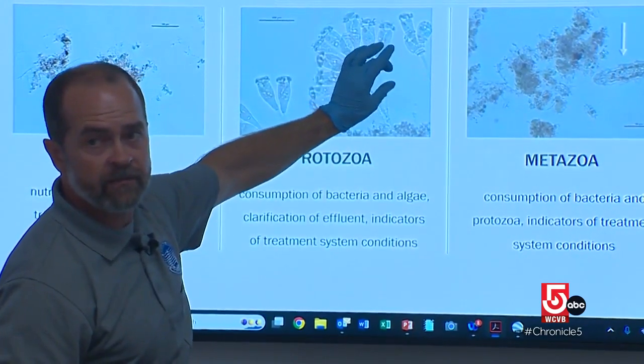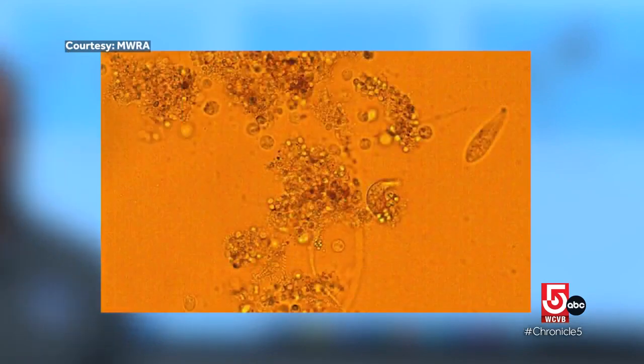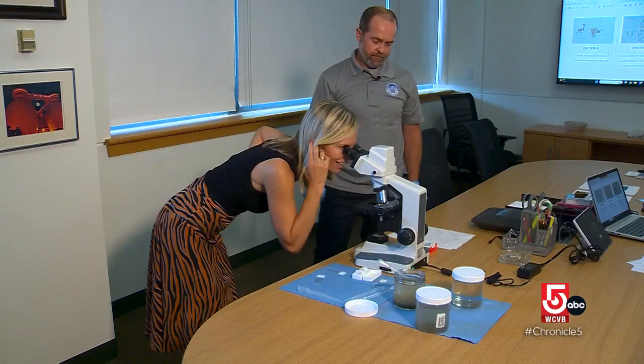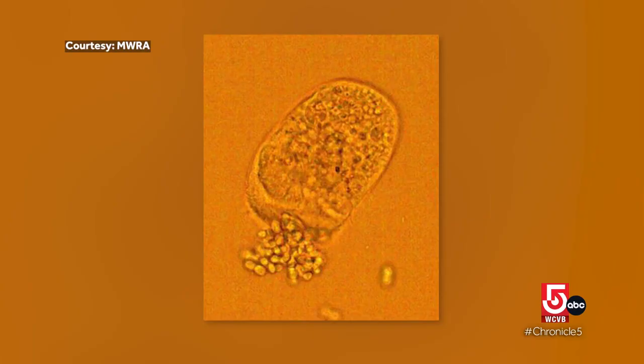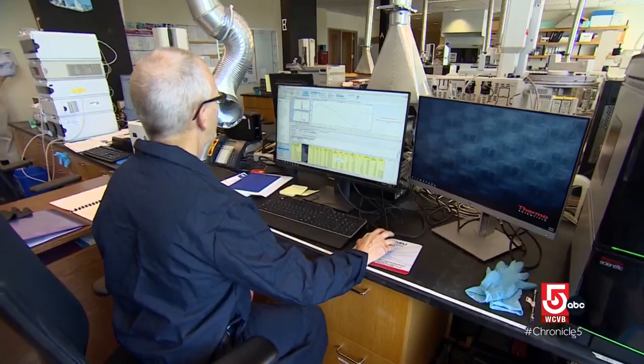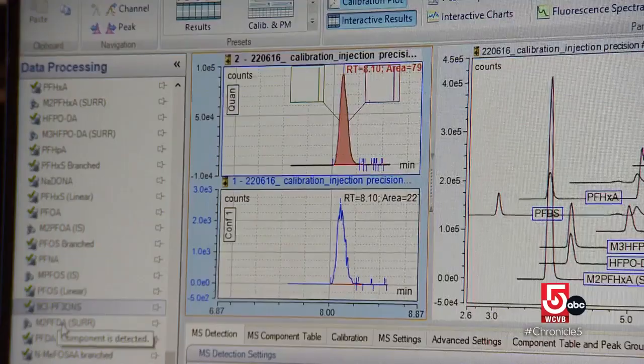Wodekowski explains some of the microorganisms crawl, some swim, but most importantly, they eat. You see it crawling around? It's got like little legs — kind of looks like a crab or something. They call those grazers. He's feasting away, breaking down nutrients. I see something that kind of looks like a flower. That's a protozoan — they kind of filter the liquid that's left. Every week, the team checks samples to make sure the system is in balance.